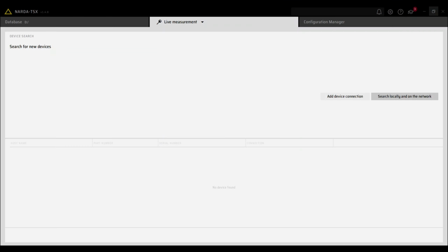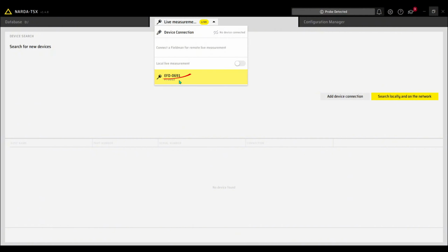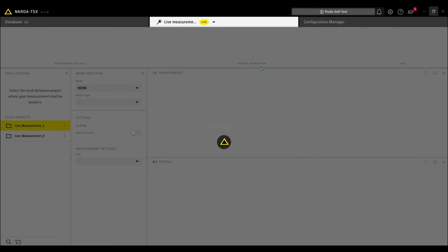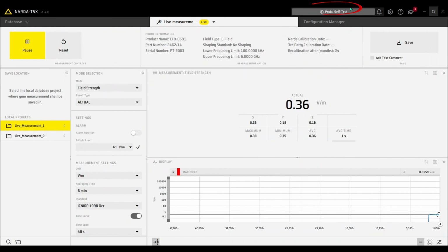And here we are on the live measurement again. So I will connect the probe. You see here, the probe is detected. And if I choose the probe, you will see the probe self-test also. And the rest is the overlay of the live measurement with the probe.